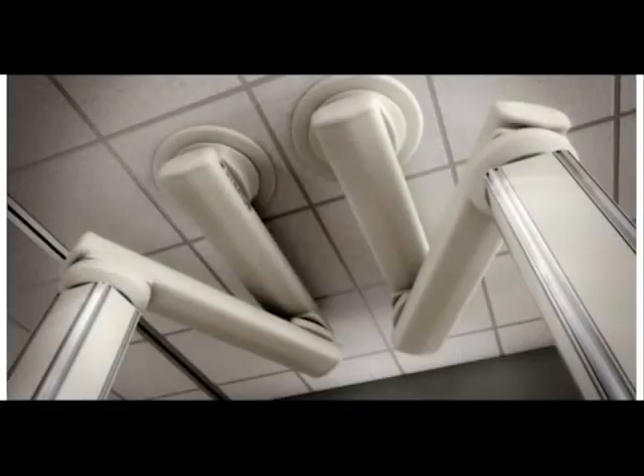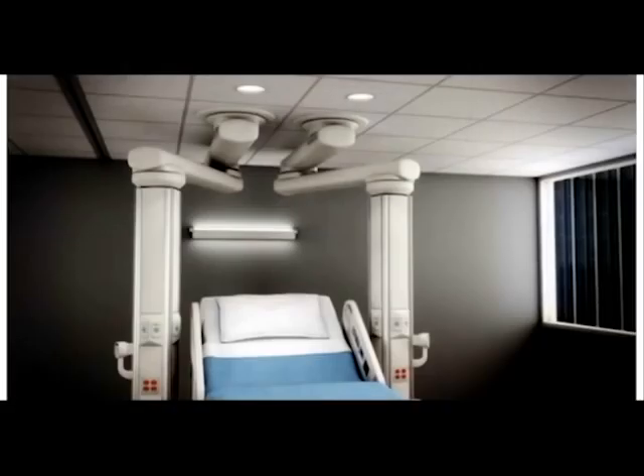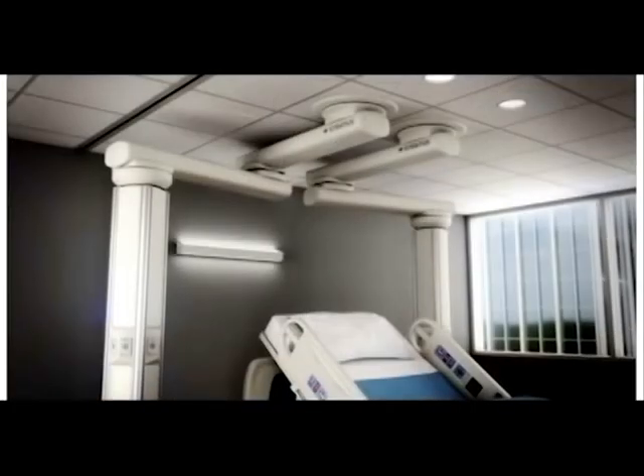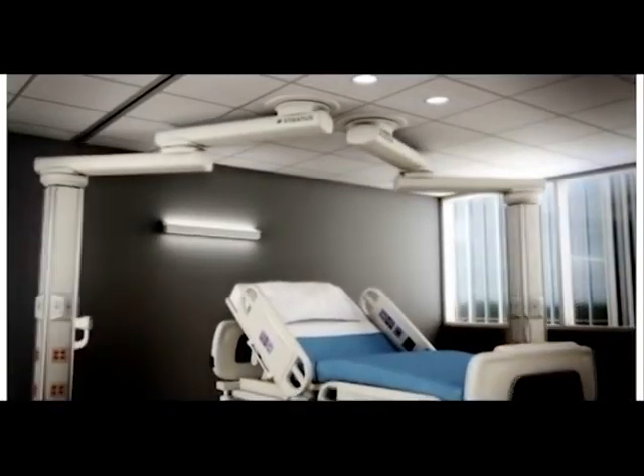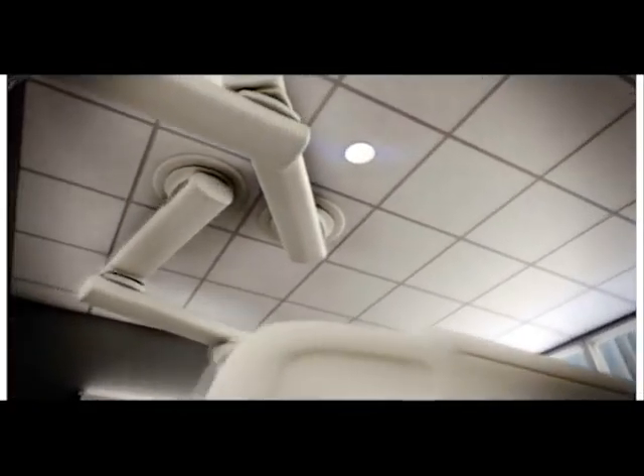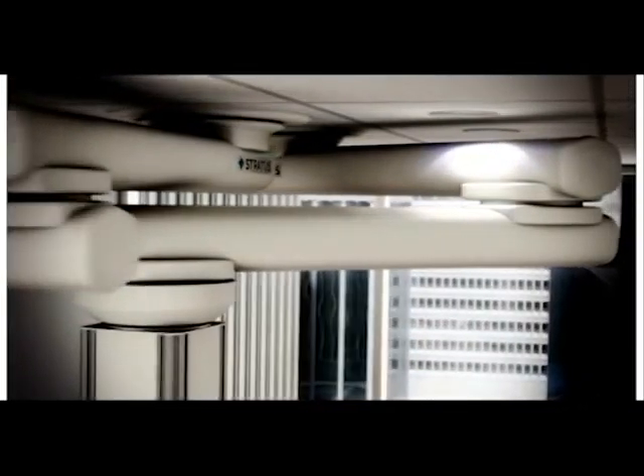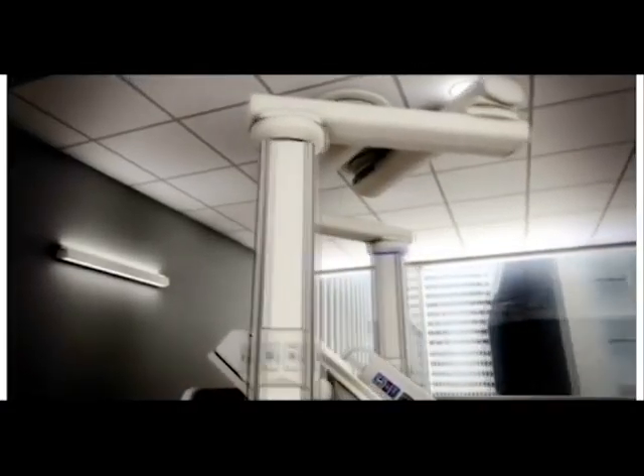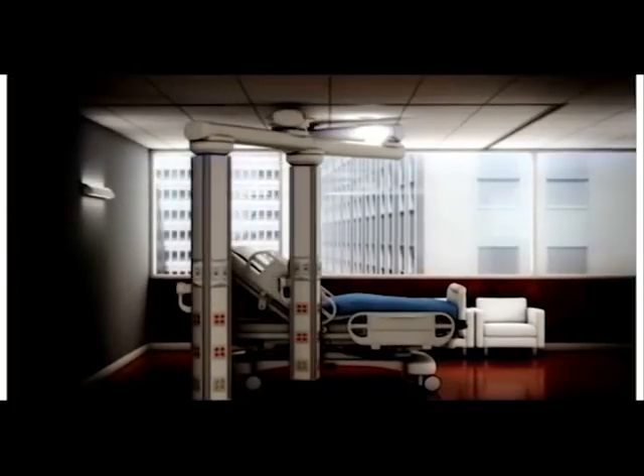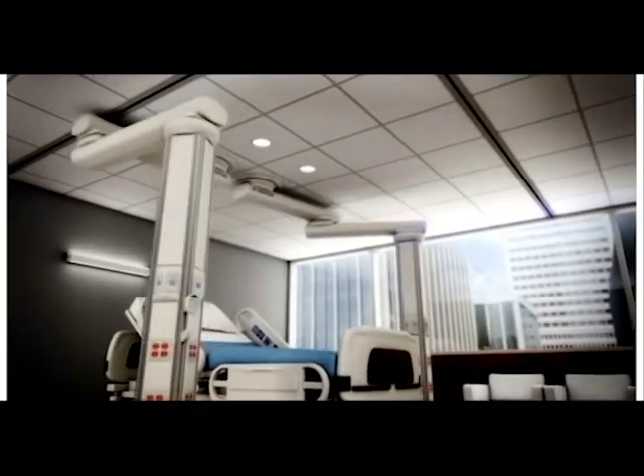The double articulated arms are capable of rotating up to 350 degrees at each joint by repositioning the user-adjustable stops. Electromagnetic brakes allow the unit to maintain position as set by the clinical staff. Release buttons are used to disengage the brakes when repositioning is required. Spatial positioning is carried out by rotational movement of the support system by means of a maintenance-free precision roller bearing. The combined arm and column assembly are capable of supporting accessory loads up to 400 pounds.